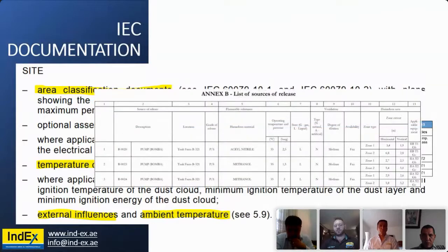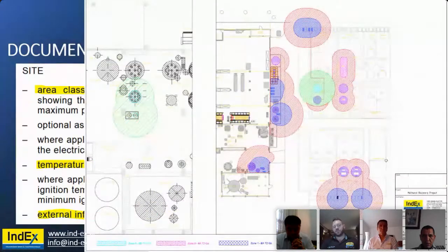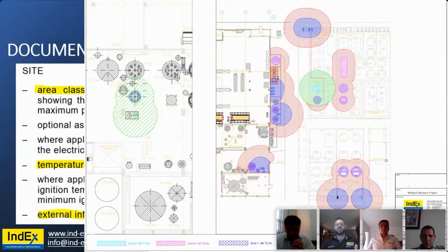Then we define the sources of release. Where is that gas coming from? Which flanges? Which valves? Which locations on the facility? We take a plot plan and overlay a drawing as to where those hazardous areas are. We give visual indications so that then the designers can source the correct equipment and the procurement can order the safe equipment that will be safe for the hazardous areas that have been defined.